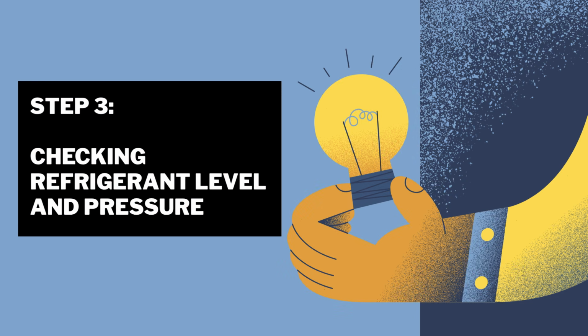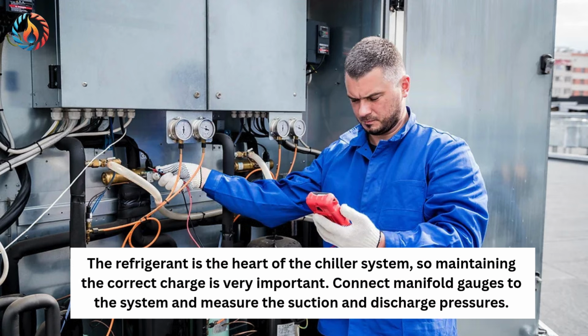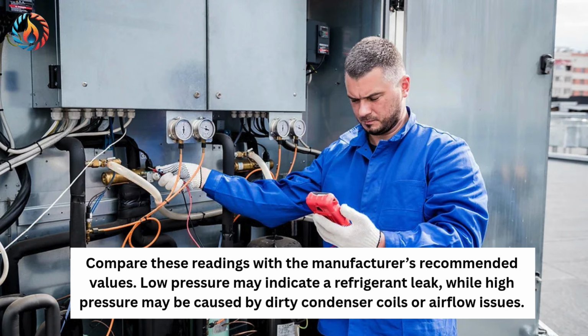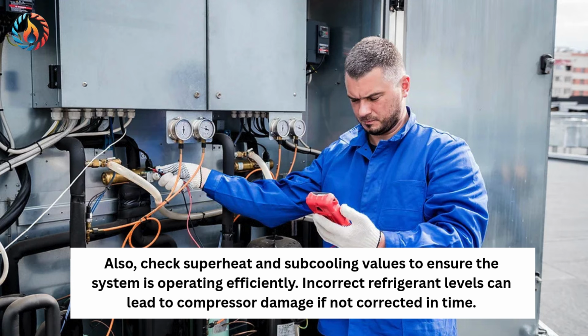Step 3. Checking refrigerant level and pressure. The refrigerant is the heart of the chiller system, so maintaining the correct charge is very important. Connect manifold gauges to the system and measure the suction and discharge pressures. Compare these readings with the manufacturer's recommended values. Low pressure may indicate a refrigerant leak, while high pressure may be caused by dirty condenser coils or airflow issues. Also, check superheat and subcooling values to ensure the system is operating efficiently. Incorrect refrigerant levels can lead to compressor damage if not corrected in time.